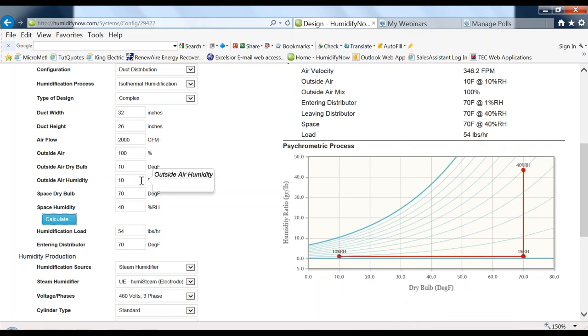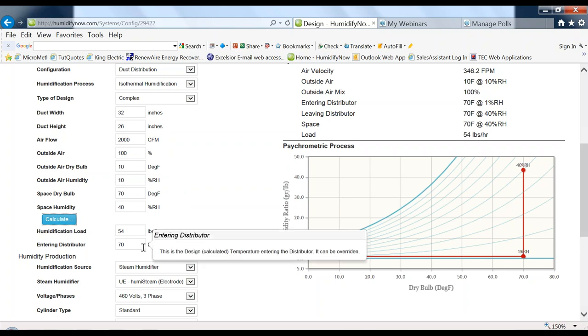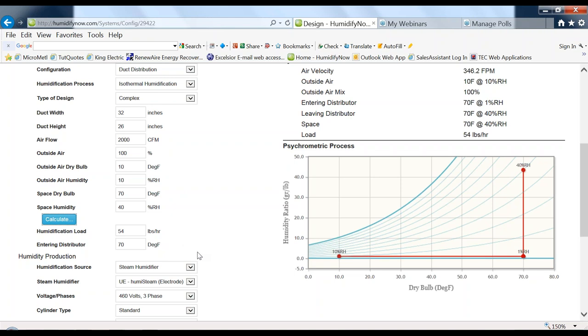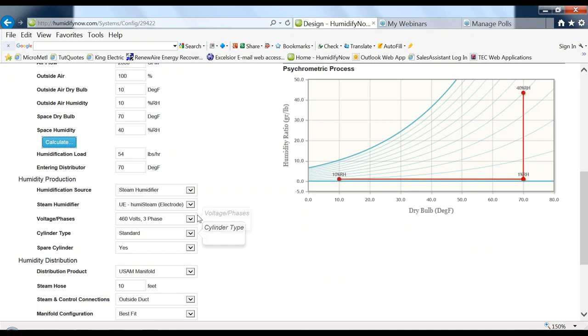When you get down to very low outdoor humidity — say 10%, 20%, 30% — the grains of moisture are pretty similar, so it really doesn't matter much at that point. The air entering the distributor determines the absorption distance, which in some cases is very critical — especially if you have a lined duct or an elbow following the steam distributor.